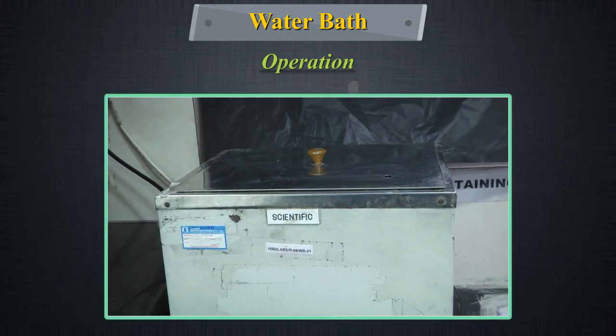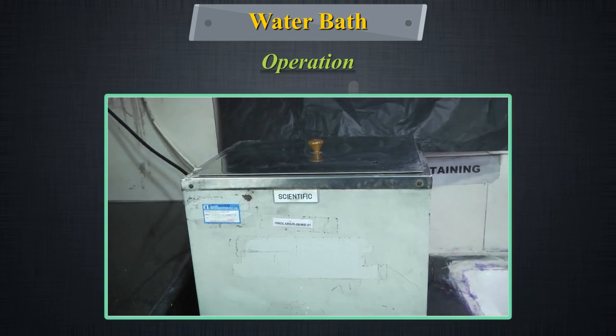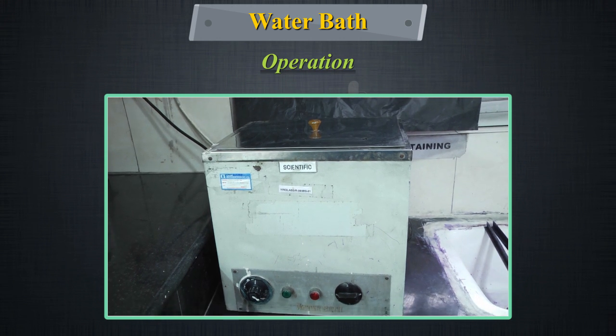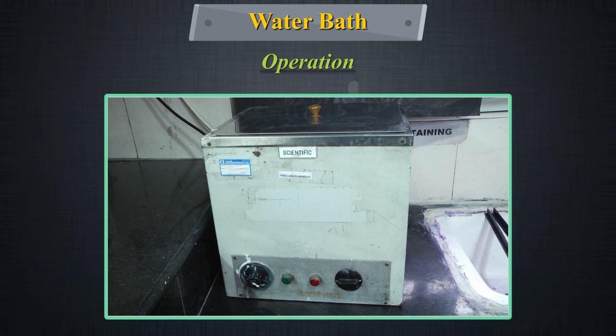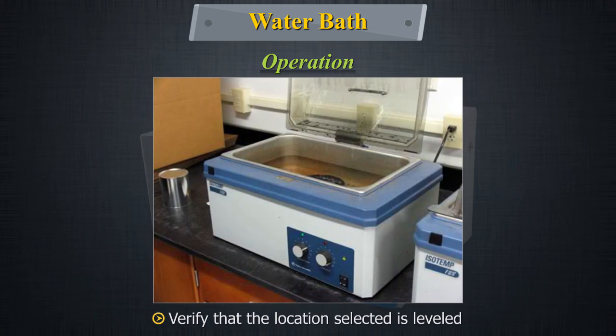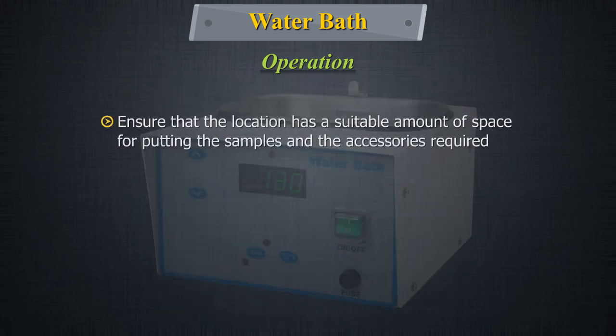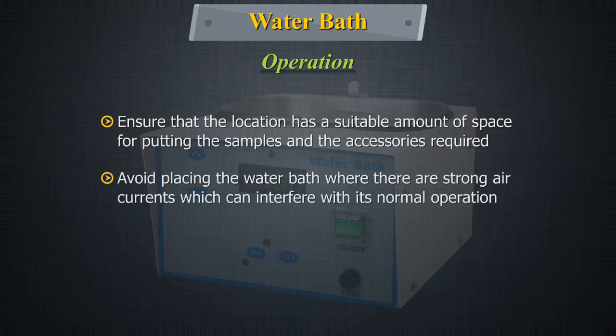For operation, install the water bath close to an electrical outlet. Its installation and use is facilitated by having a sink close by for supplying and draining of water. Verify that the location selected is level. Ensure that the location has a suitable amount of space for putting the samples and the accessories required. Avoid placing the water bath where there are strong air currents which can interfere with its normal operation.